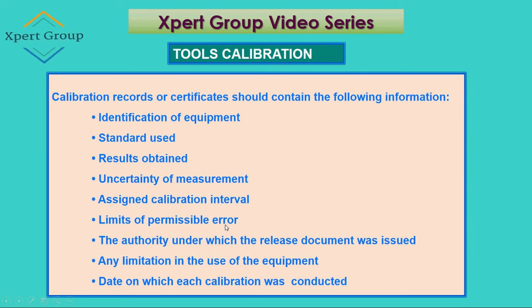Limits of permissible error — any allowed permissible error limits should be mentioned in the record. The authority under which the release document was issued should be mentioned. Any limitation in the use of the equipment should be mentioned by the calibration organization from where you are getting the calibration. The date on which each calibration was conducted should also be recorded, meaning you should have a good record of dates when you conducted the calibration of that specific tool.